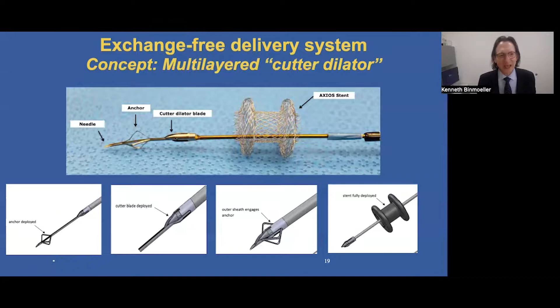delivery system. And so this has a ceramic bougie-shaped tip, and we have cautery micro wires alongside the conical tip, and then also converging at the very tip in a circular fashion, so that we are distributing the cautery over a very small surface area. So we maximize the cutting effect and minimize the coagulation effect.